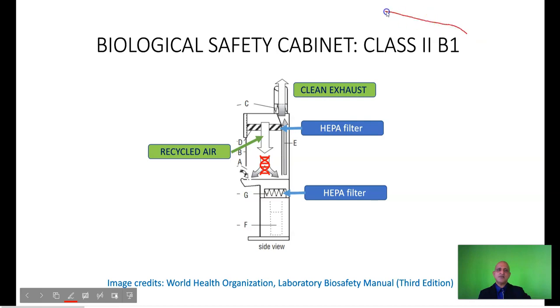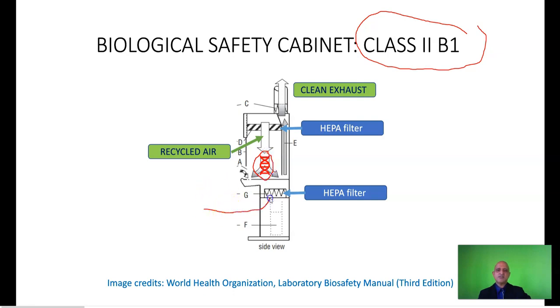Okay, this is how the class 2 B1 cabinet actually works. We have the biological agent here, which I've indicated as a DNA molecule, and the air is drawn through these HEPA filters. The air which enters onto the top of the bench is HEPA filtered, and it exits through this small grill at the bottom, as well as over the specimen or the biological agent itself, and then it's exhausted through the facility via the HEPA filter. Again, the technical term, if it is linked to the external environment, is a hard ducted cabinet. However, if it recycles the air through your facility itself, it is not considered hard ducted. It's allowing the air to filter back into the facility. So this depends on your engineering design. You have to take into account the fact that exhausting large amounts of your filtered air from your facility may result in an increased load on your air conditioning system. This must be discussed with your engineers.